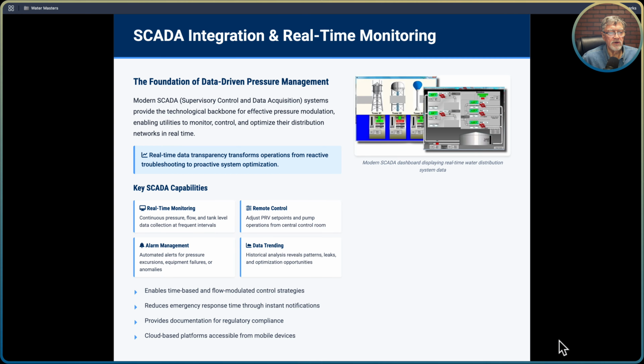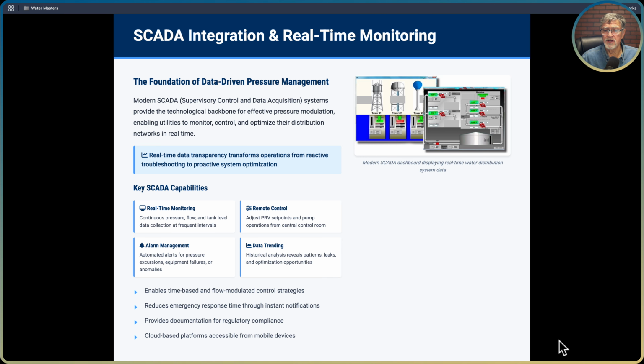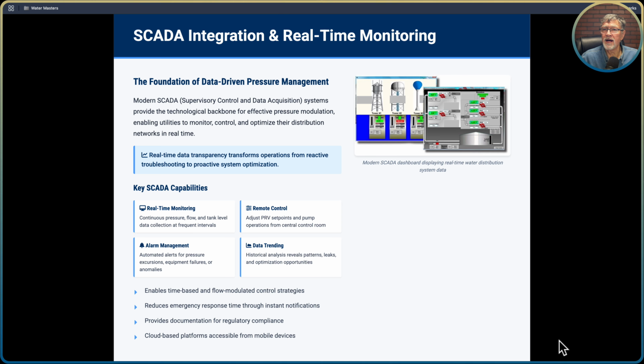All right, so the foundation of data-driven pressure management: modern SCADA systems. For those that don't know, SCADA stands for supervisory control and data acquisition, and that's kind of the heart of your water treatment plant. They provide the technological backbone for effective pressure modulation, enabling utilities to monitor, control, and optimize their distribution networks in real time. And quite frankly, they do a lot of things. They monitor your wells, your pumps, and your tank levels. There's a lot that SCADA does that it didn't used to do, and these have become a lot more sophisticated and a lot less expensive too. So more capabilities for lower costs.